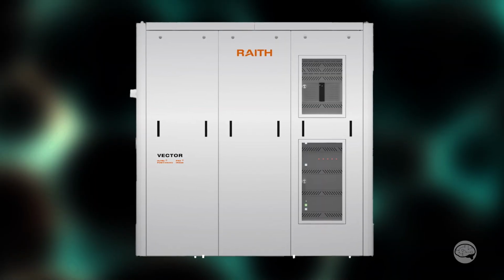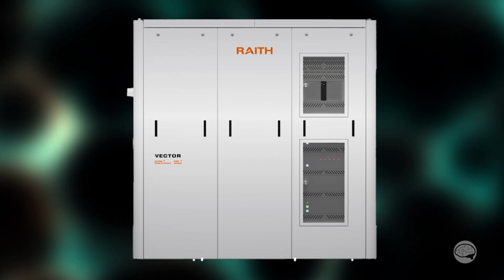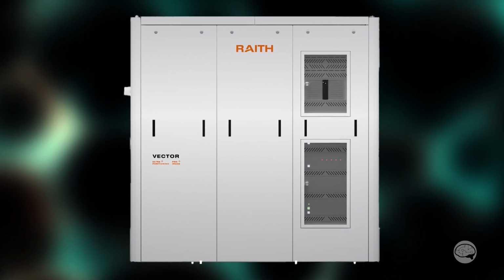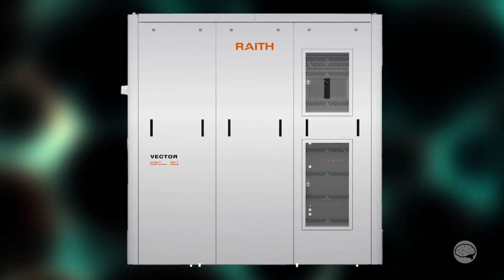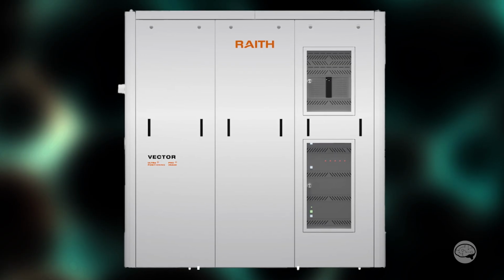So some of the key features are hardware-based. It has a laser interferometer-driven stage, so really excellent placement accuracy across a really large range of motion. Across a 6-inch wafer, within 100 nanometers placement accuracy anywhere you navigate. And if you're willing to confine yourself to a smaller field of view, it could be less than 10 nanometers accurate.